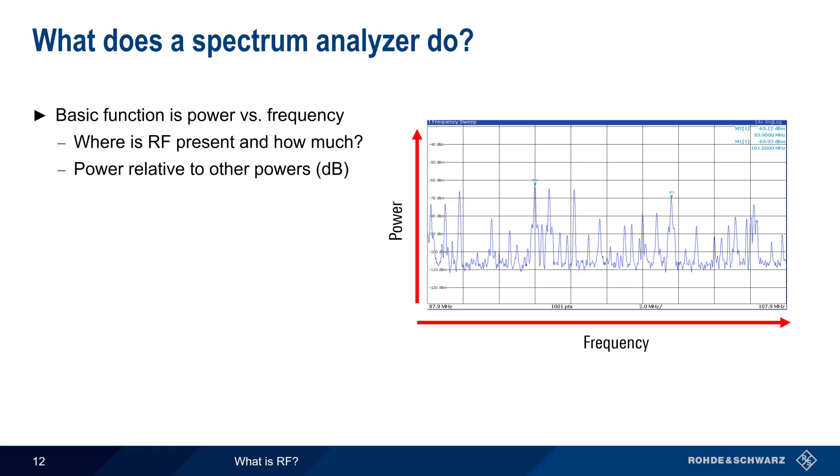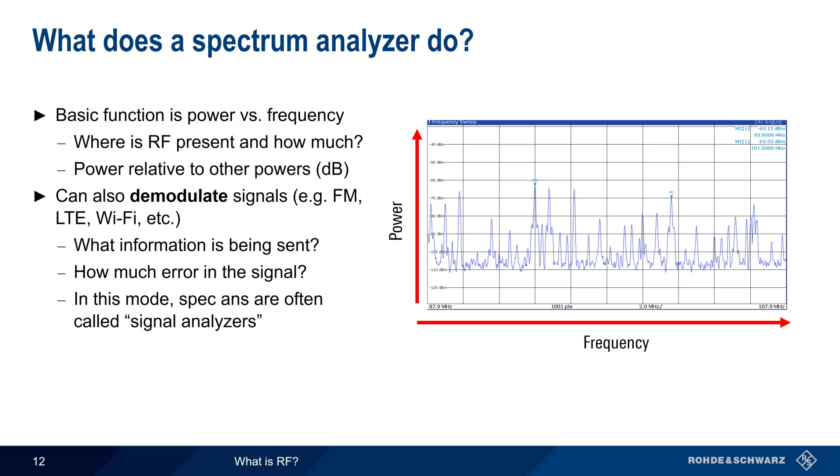In addition to the basic power versus frequency display, many spectrum analyzers can also demodulate different types of signals. These can be very basic analog signals, like those used in FM radio, or it can be quite complex digital signals, like those used in LTE, 5G, Wi-Fi, etc. Demodulation means extracting the information in a signal, but can also be used to tell us things like how much error or inaccuracy there is in a modulated or information-carrying signal. When a spectrum analyzer is used in this way, it is often referred to as a signal analyzer.